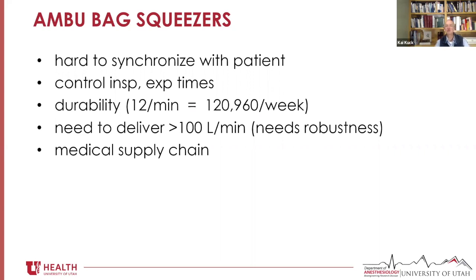Drugs for sedation are running short right now globally. So they're already moving from propofol, which they usually would use, to midazolam and other things. So even in these last resort type ventilators, you've got to have some way of having the patient trigger a breath. And that would be really difficult in these squeeze and ambu bag kind of machines. Just like what you said, Lars, controlling inspiratory and expiratory times, how do you do that? How do you say, okay, I have a breath, and the first third should be inspiration and the last two thirds should be expiration? How do you balance that? How do you create the precise pressure control that you would need, and the PEEP?